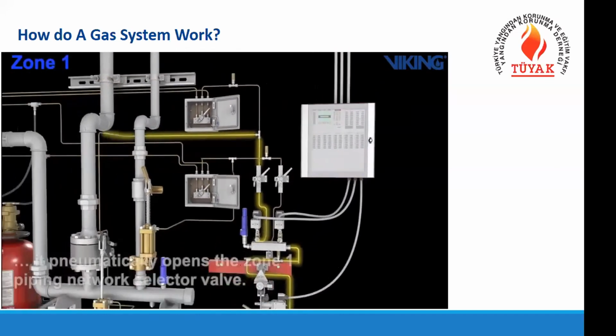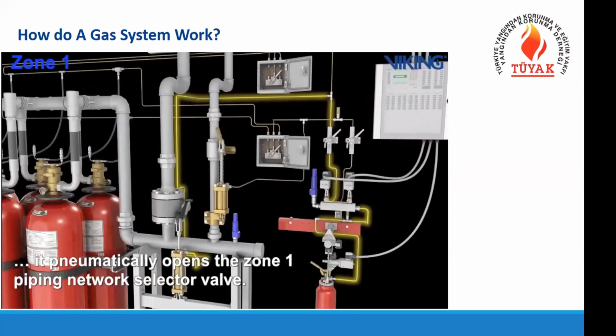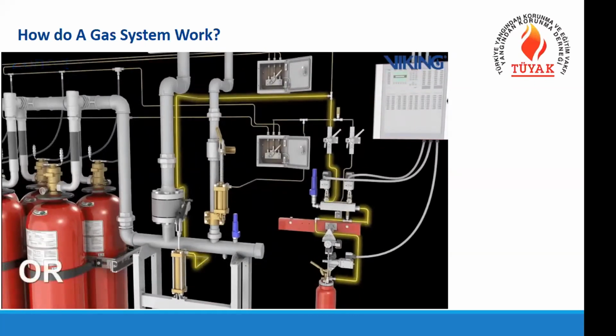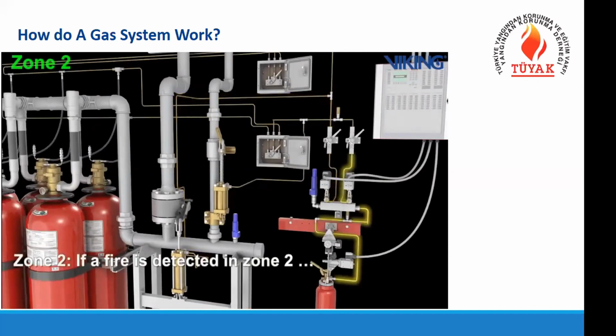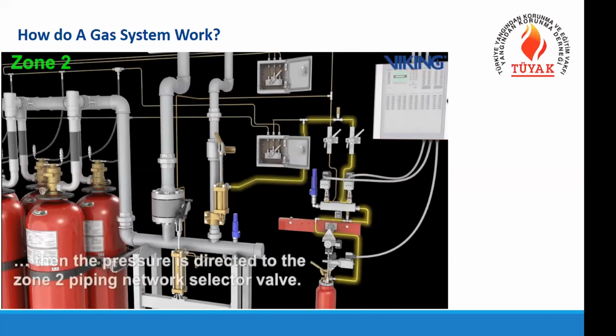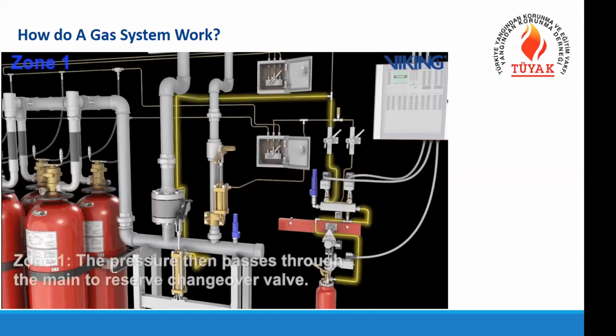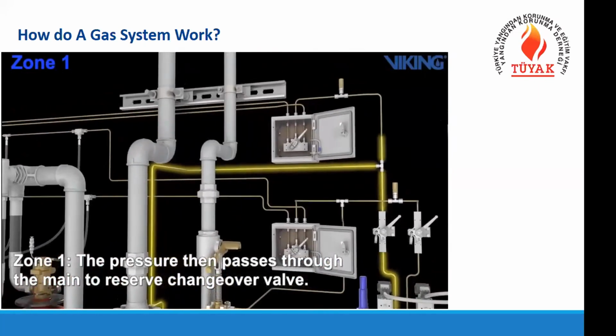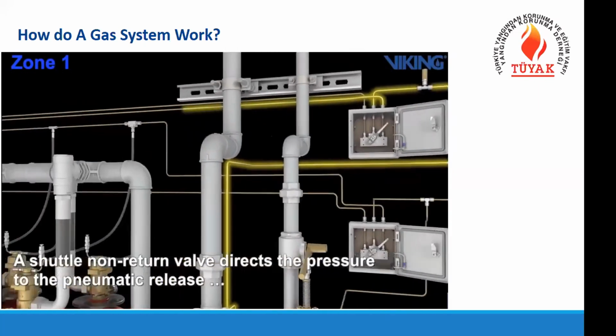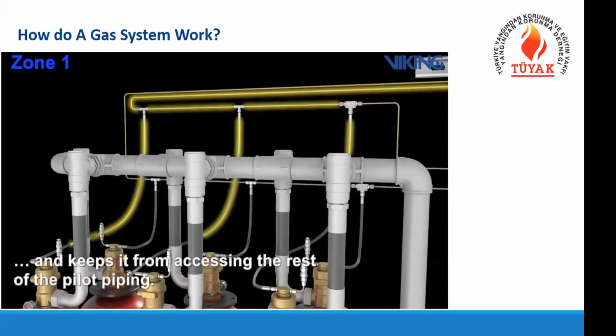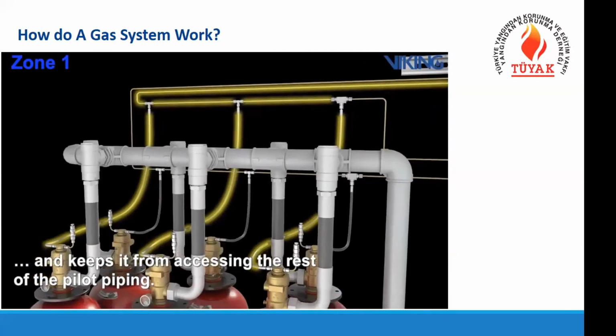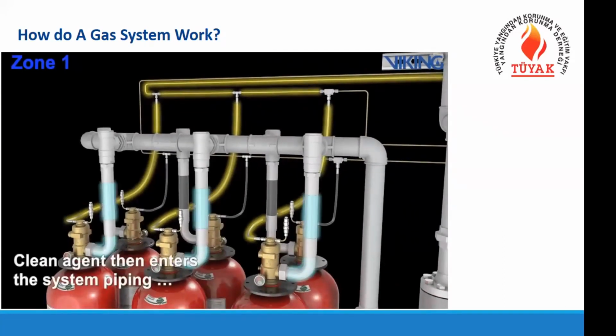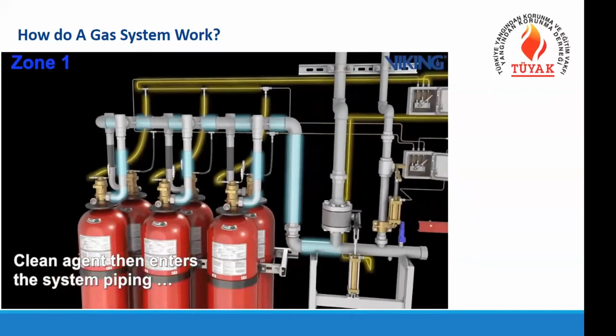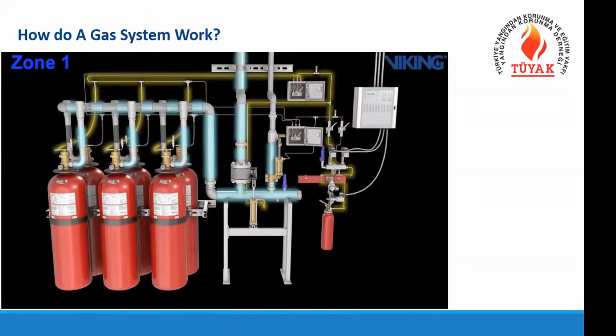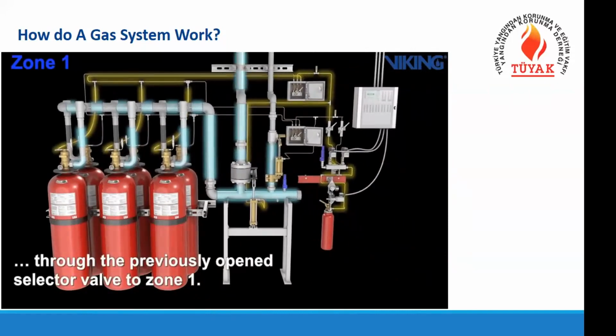In this case, this is zone 1, and the selector valve is opening. Otherwise, if instead of zone 1 the zone 2 gives an alarm, the zone 2 valve opens. When the zone 1 valve opens, the gas system is actuated by another pilot system, and it discharges just the necessary amount of gas from the necessary number of cylinders. These are the main cylinders for the bigger room, zone 1, and the gas is going to the related zone 1.